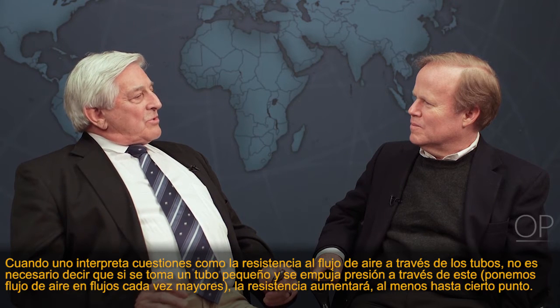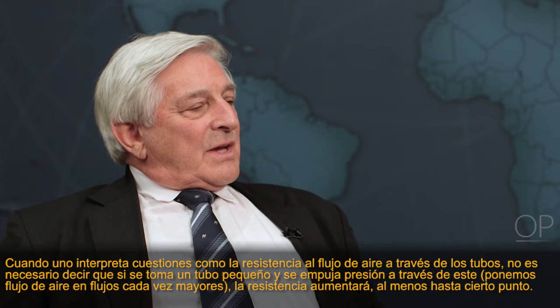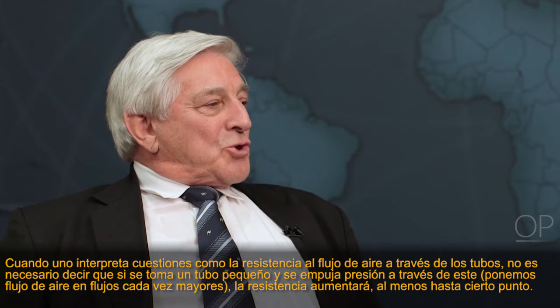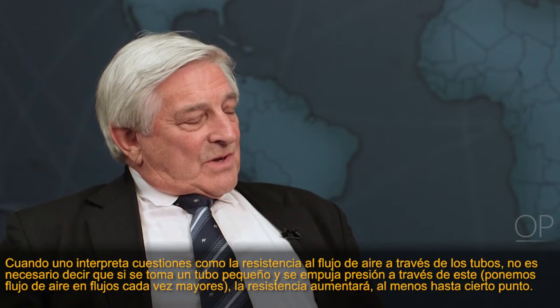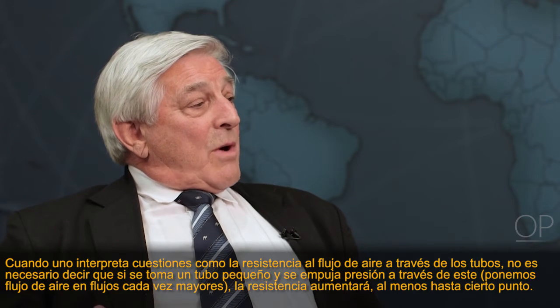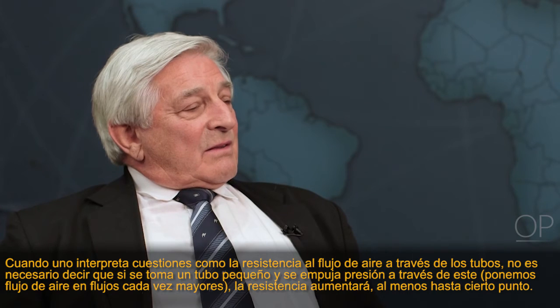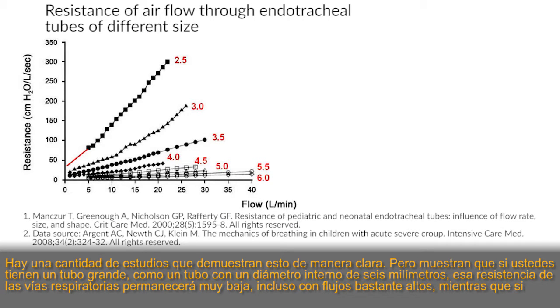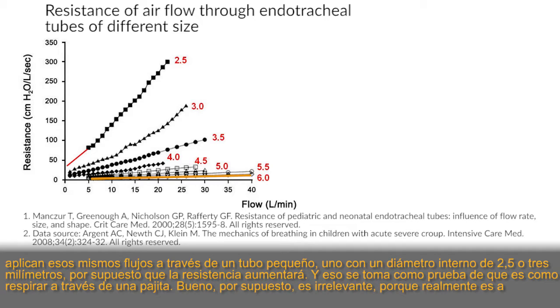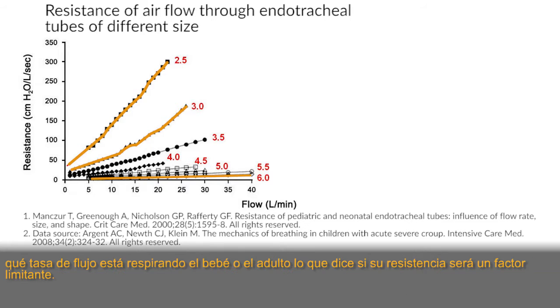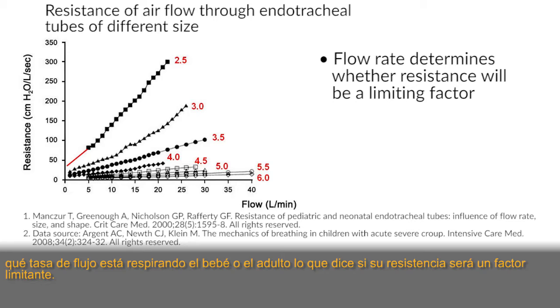When one interprets issues such as resistance to airflow through tubes, it goes without saying that if you take a small tube and you push pressure or airflow through it at higher and higher flows, the resistance will go up, at least to a certain point. And there are a number of studies which demonstrate this very clearly, but they show that if you have a big tube, like a 6 millimeter ID tube, then airways resistance will remain very low, even at quite high flows. Whereas if you put those same flows through a small tube, a 2.5 or a 3 millimeter ID, of course the resistance will go up. And that is then taken as proof that it's breathing through a straw. Well, of course, it's irrelevant because it really is at what flow rates the infant or the adult is breathing that tells you whether resistance is going to be a limiting factor.